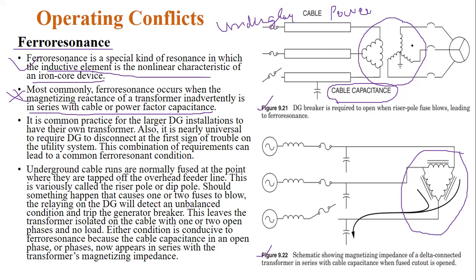So at the substation, remember, they are connected to the transformer, for suppose by using some codes we can call it a riser pole. What is a riser pole? These are the underground cables, one, two, three. In the substation, these underground cables come outside and are connected to a pole, which you can call the riser pole. They are connected through the fuse. See this fuse: three fuses for three cables, because this is a three-phase system.